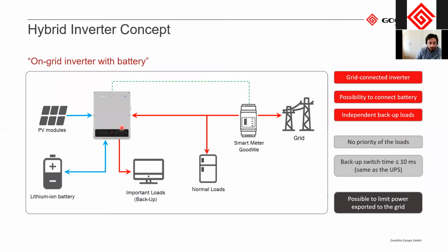For those of you who are new to the hybrid inverter concept, here's a short description. Basically, it's a grid connected inverter. It's not an off-grid inverter. It's a PV inverter with the possibility to connect a battery. Additionally, our inverters, which I will go into later, have a backup output. This means you can choose some loads in your household to connect here. In case of a grid failure, the inverter will disconnect from the grid, but keep supplying the backup loads as long as you have enough power from the PV and the battery.